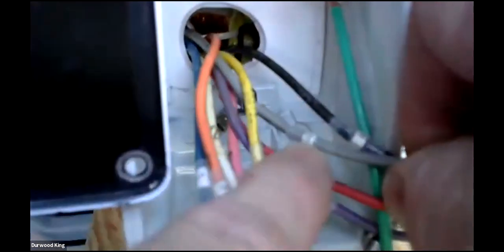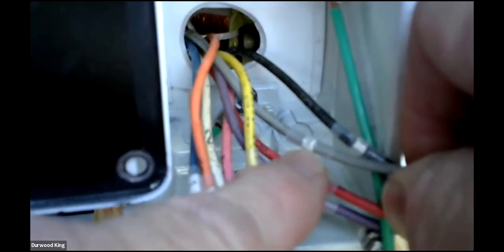And then I just lost a wire nut for 6 and 9. So there goes a 9 with a dot. There's a dot there at the bottom of the 9. So on your wire labels, they'll either have a line under the number to know whether it's a 6 or a 9, or there'll be a period, a decimal on the bottom right of the wire number, so that you can recognize what the digit is. Now, I know my camera is not detailed enough to be sharp on that. But I have ordered a better camera. We're going to put 6 and 9 together there.